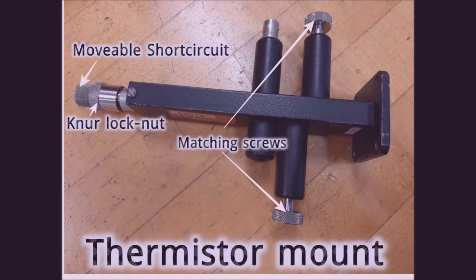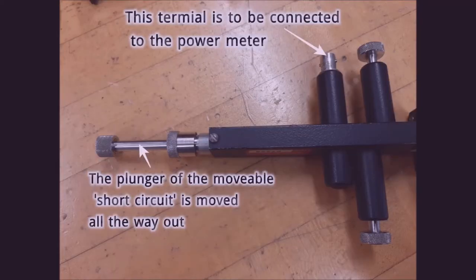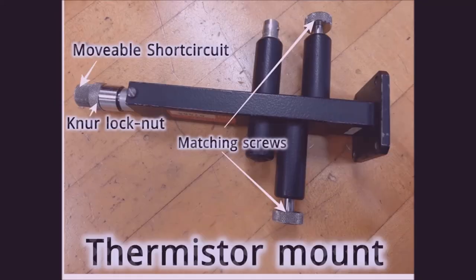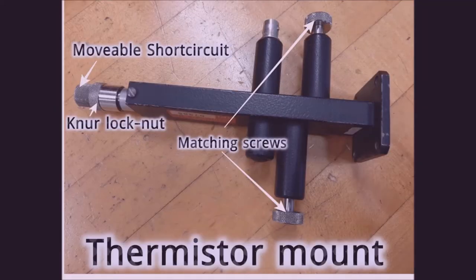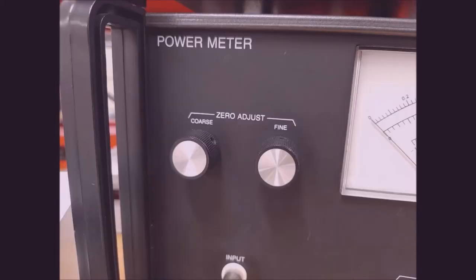The actual look of the thermistor mount is shown in this photo — the matching screws and the movable short circuit are labeled. The short circuit can be moved inward and outward; a knob lock holds it in position. The thermistor is connected to the input port of the power meter. Power readings can be obtained from the dial; we can read power in both milliwatts and dBm. The range selection buttons select the proper range — the highest range is 10 milliwatts. The zero-adjust knobs are used to zero the meter.